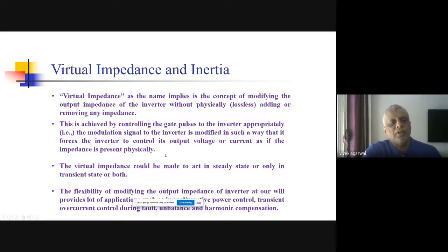So what exactly do we mean by virtual impedance, and what do we mean by inertia? As I explained earlier, inertia in the conventional system versus the microgrid system isn't really there physically, but it appears to be there. Your system behaves as if that inertia is present, though it isn't. This is done through control loops.